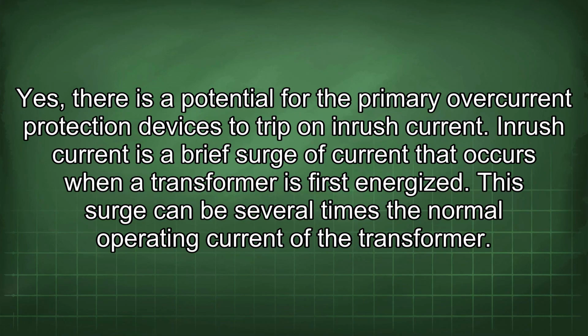Yes, there is a potential for the primary overcurrent protection devices to trip on inrush current. Inrush current is a brief surge of current that occurs when a transformer is first energized. This surge can be several times the normal operating current of the transformer.